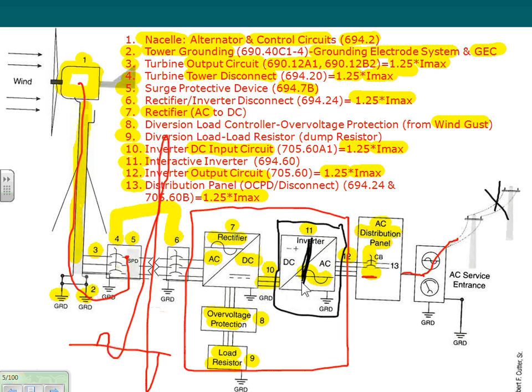Now the question would be, well, I lost the grid and I lost the wind at the same time. That's exactly why, right here, there is a system, an inverter that has a bypass where if you lose the grid, it diverts the wind power to another panel, and you can feed certain loads in your building. So you can have a source right in here going to a second panel, where upon the loss of the utility, you isolate your system, and then we divert the power into another panel.